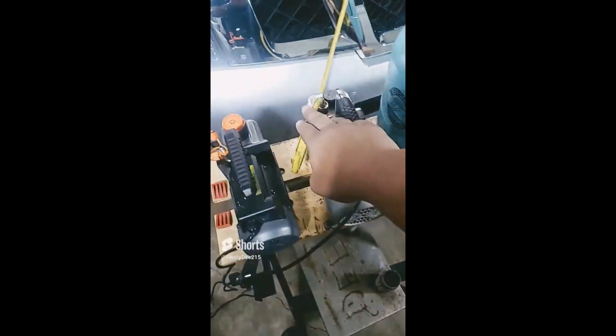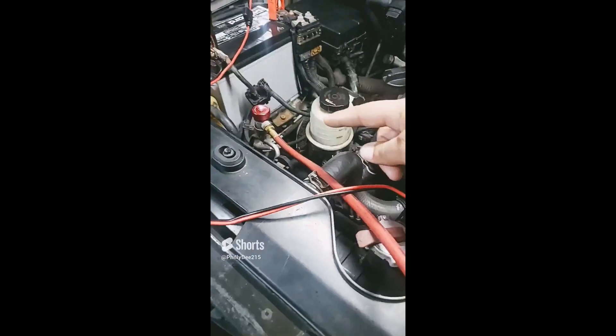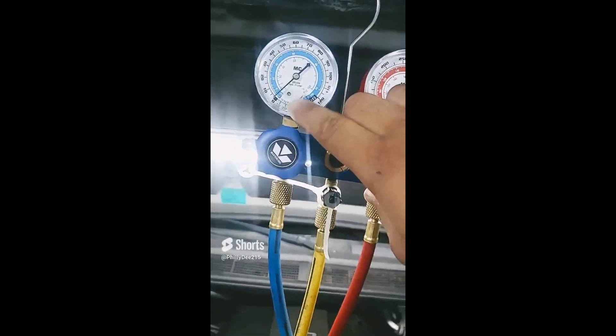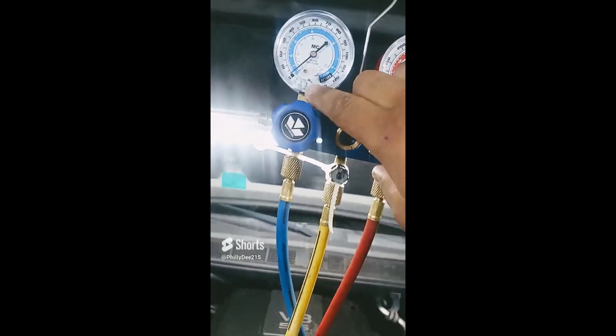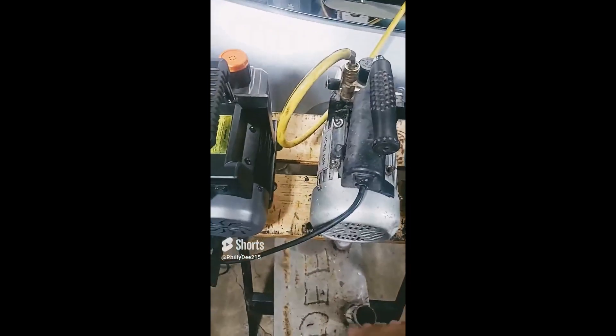So we got it hooked up. I got the low side and the high side hooked up. So I'm going to show you how this pump won't pull down the vacuum, and I'm also going to show you what it sounds like when it's bad.